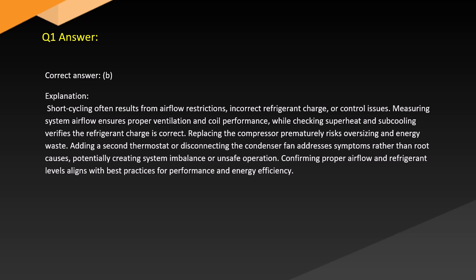Short cycling often results from airflow restrictions, incorrect refrigerant charge, or control issues. Measuring system airflow ensures proper ventilation and coil performance, while checking superheat and subcooling verifies the refrigerant charge is correct. Replacing the compressor prematurely risks oversizing and energy waste. Adding a second thermostat or disconnecting the condenser fan addresses symptoms rather than root causes, potentially creating system imbalance or unsafe operation. Confirming proper airflow and refrigerant levels aligns with best practices for performance and energy efficiency.